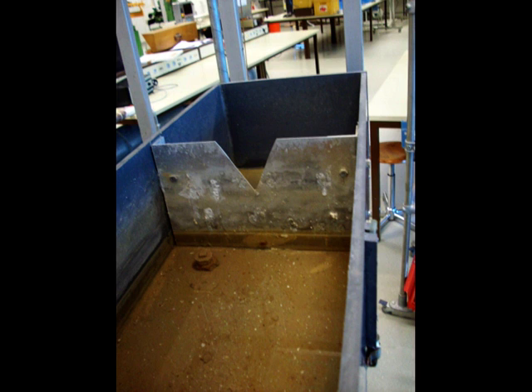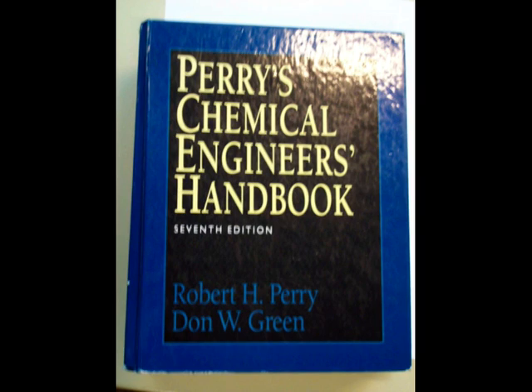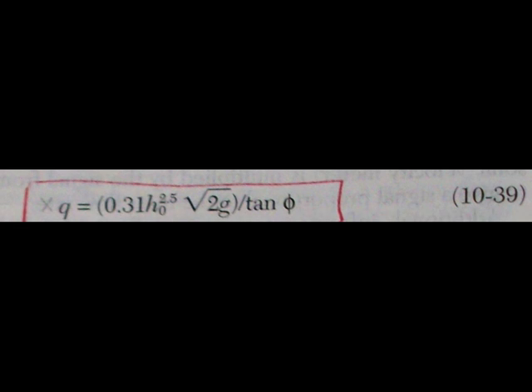If you want to measure the flow through the channel accurately you have to determine the angle of the triangular overflow. If you then go to the library you can find formula 10.38 in the Perry's Chemical Handbook and that will show you how you have to calculate the flow through that channel.